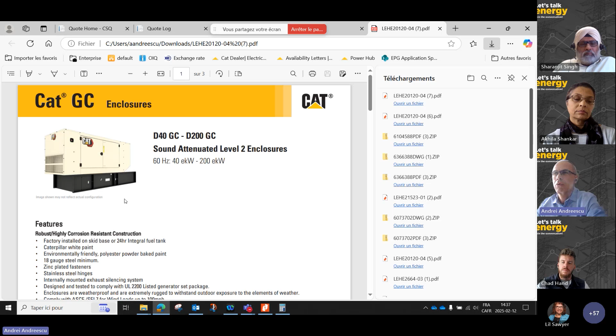Once we download, we have access to the spec sheet - the same picture we saw while configuring the generator, with full detail of the enclosure. For the 125 kilowatt generator we selected, the enclosure offers a noise level of roughly 75 dBA at 7 meters, with specific dimensions and weights for the unit with the fuel tank. So you have full access to the documentation.